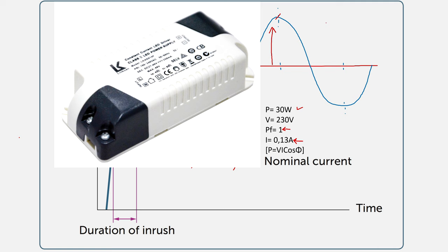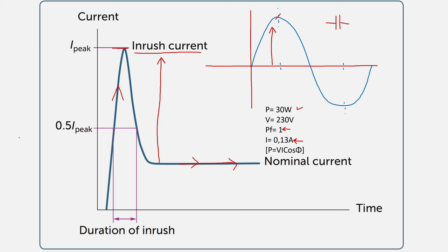Most LED floodlights utilize a driver circuit, and that driver circuit often uses a capacitor. A capacitor charges as soon as we apply a voltage across its terminals — and that is what this high inrush current is: the charging of the driver circuit. If we happen to turn on the floodlight at the zero crossing — maybe 180 degrees or zero — we would have a much lower inrush current, because the capacitor would charge as the voltage waveform increased.